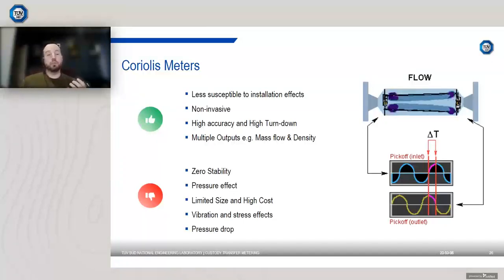And they also tend to be fairly accurate and have a high turndown. So they've got a higher turndown typically than the traditional technologies, and you can get uncertainty as low as 0.1% or better. Again, it depends on the calibration route and things like that.